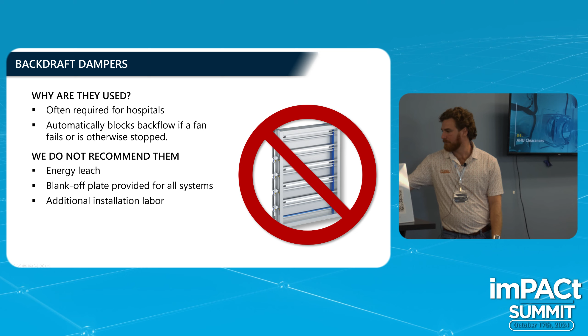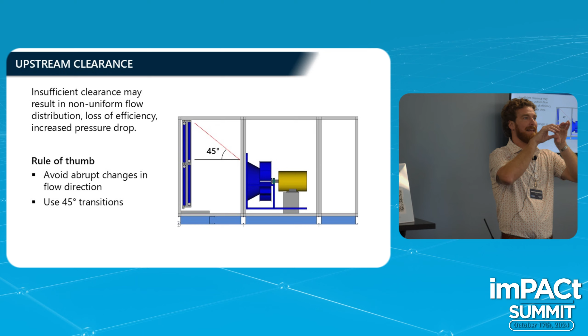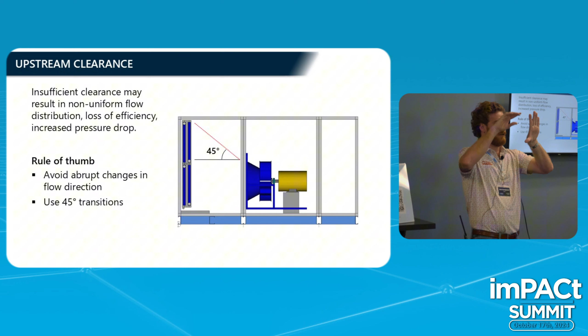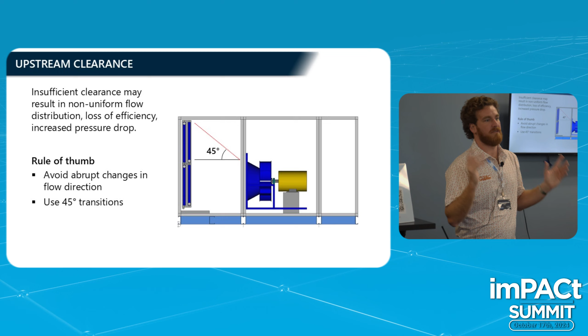Okay, for clearances, the rule of thumb here is that 45-degree transition. If you take your fan inlet and draw a box, a rectangle, around the edges of the inlet cones where they're tangent to that line, and you have a 45-degree angle from that to the edge of the coil, you're good. You really want to maintain either that 45 or a larger angle. Once you get lower than that, you can have some stratification issues with the airflow through the coil. In general it's not a huge deal, but it can be an issue if you have a large enough system or a smaller coil face. So that's just a rule of thumb, that 45-degree angle.